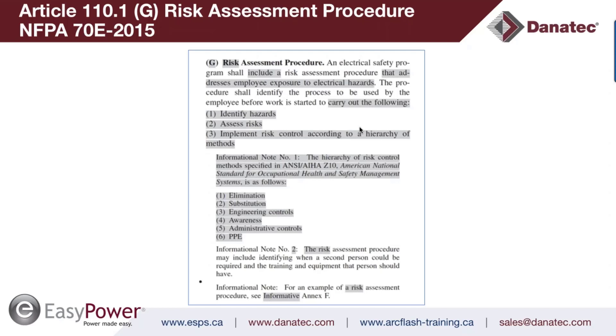The procedure shall identify the process to be used by the employee before work has started: identify if they are exposed to arc flash and shock hazards, assess risks related to the work task, and implement risk control according to the hierarchy of methods. The hierarchy of methods was an informational note in the 2015 edition quoting ANSI Z10. In the 2018 edition, that informational note moves into a sub-article — making it mandatory to consider all hierarchy of controls from top down, not bottom up.